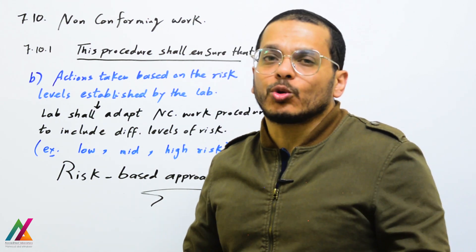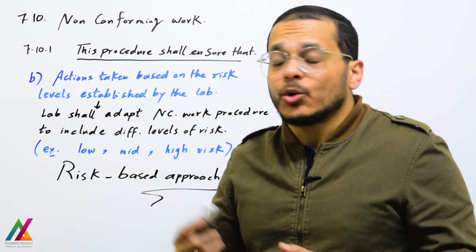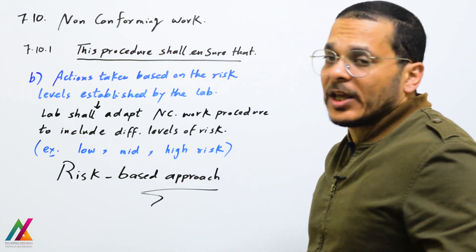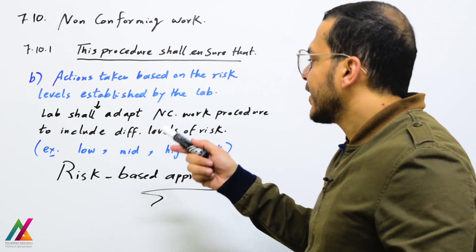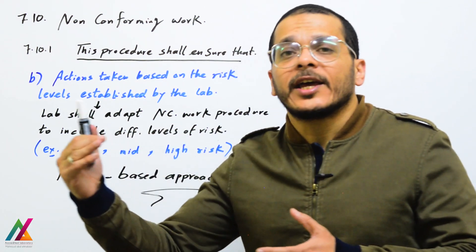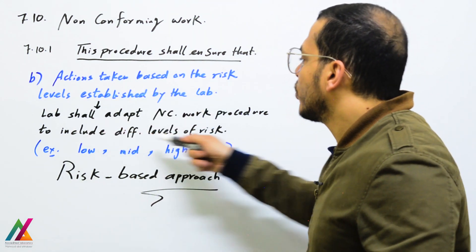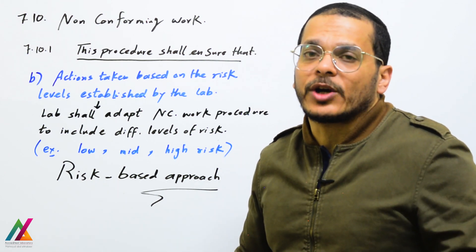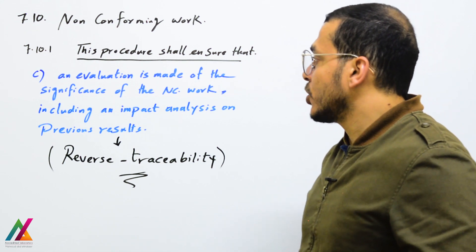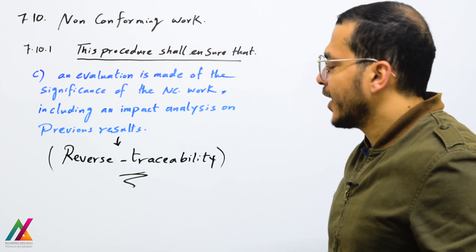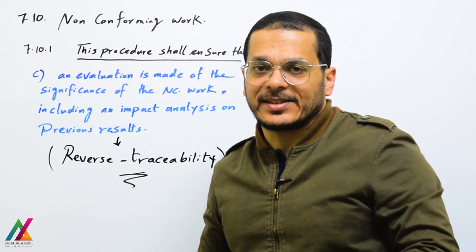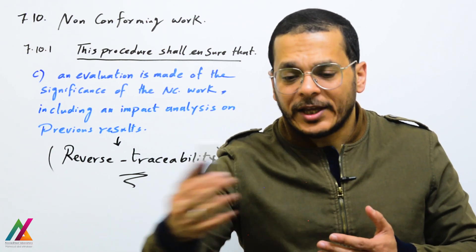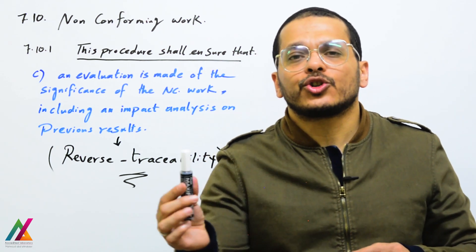Because the risk-based approach is newly added to this edition, it is a valid point to add to this procedure. Actions taken will be based on the risk levels established by the lab. The lab shall adapt the non-conforming work procedure to include different levels of risk — low, mid, or high — and take action based on risk type. Additionally, an evaluation shall be made of the significance of non-conforming work, including an impact analysis on previous results, which is called reverse traceability.